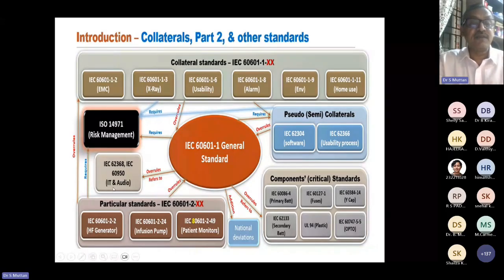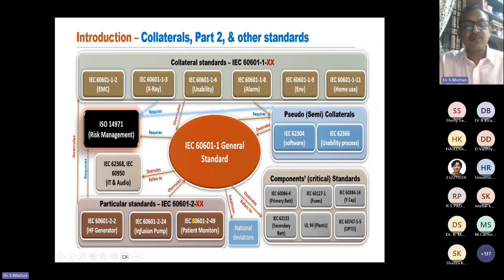Then if it is in the field of IT and audio, these have to be taken. And this is a particular standard if it is for a high frequency generator, infusion pump, or patient monitoring system. If it is a patient monitoring system, yes, you have to go through this standard. If it is a ventilator, there is another standard. If it's an X-ray machine, there is another standard. So like that it goes.